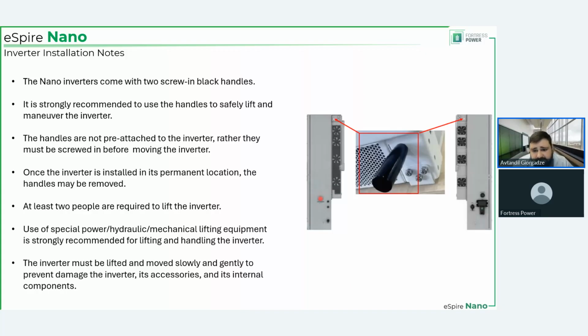The inverter is, as I said, 200 pounds. One person is not lifting it, and you might need special equipment, or at least 2 people, depending on what those people are comfortable with doing. If they're comfortable with lifting 200 pounds and putting that onto the wall bracket, that's fine. But I would strongly recommend using power equipment. Some kind of portable crane could be used. A lift jack, if you can find one that is useful for this purpose, can be used. A forklift could technically be another option, but I would not recommend it.